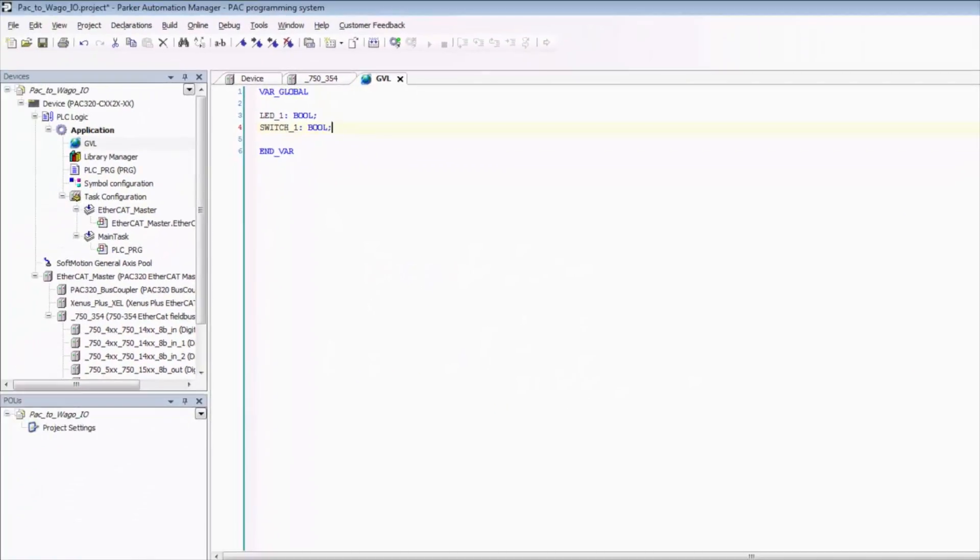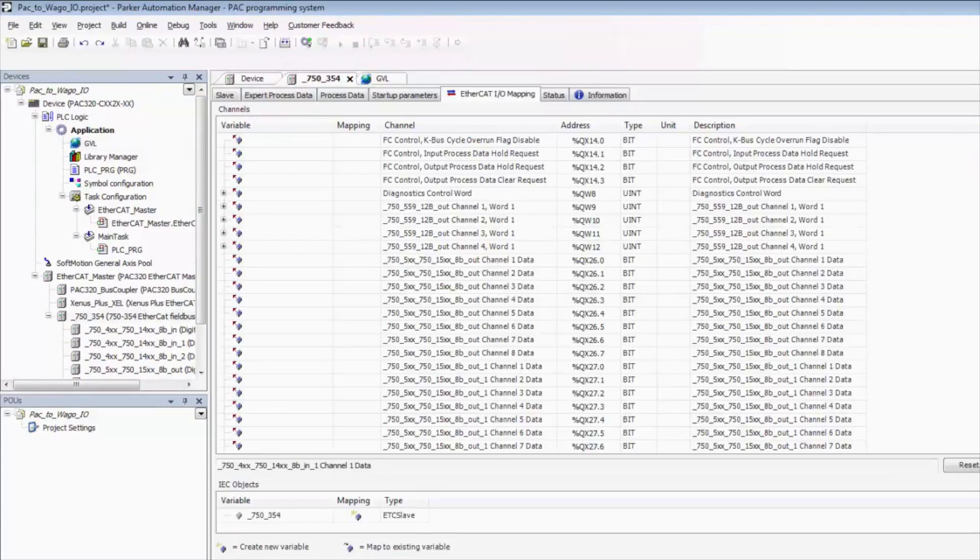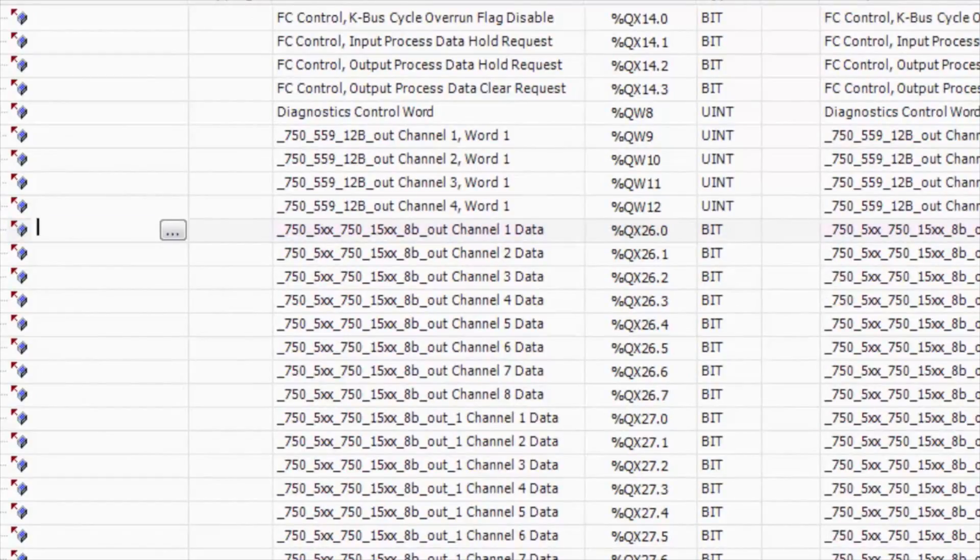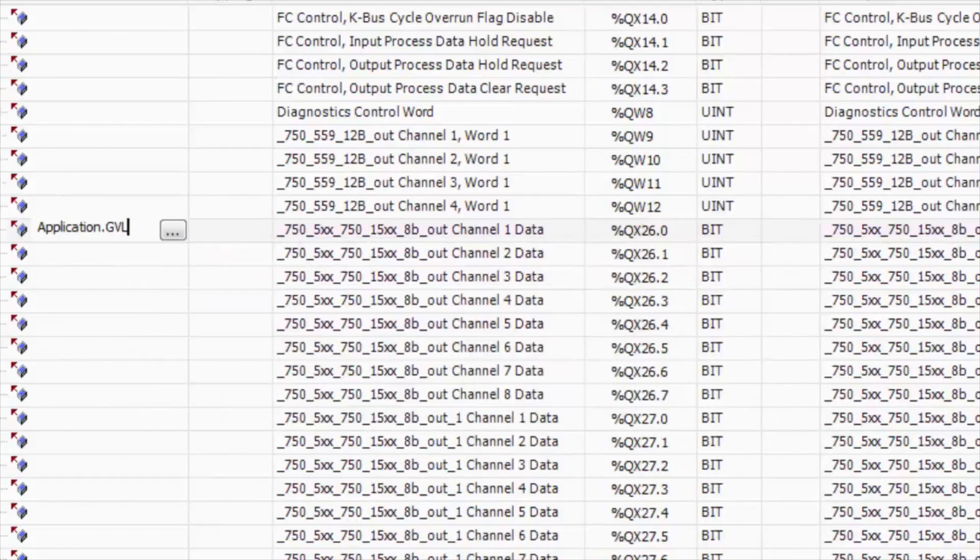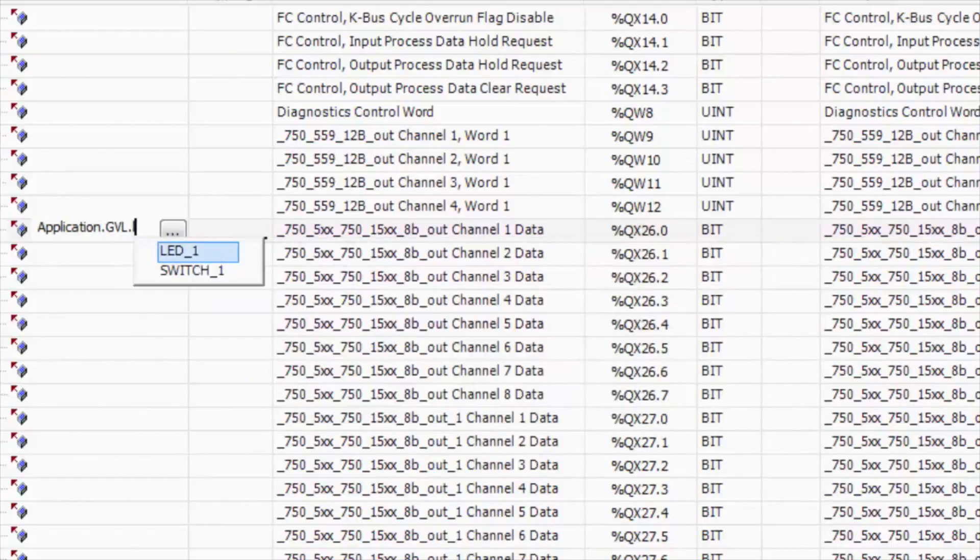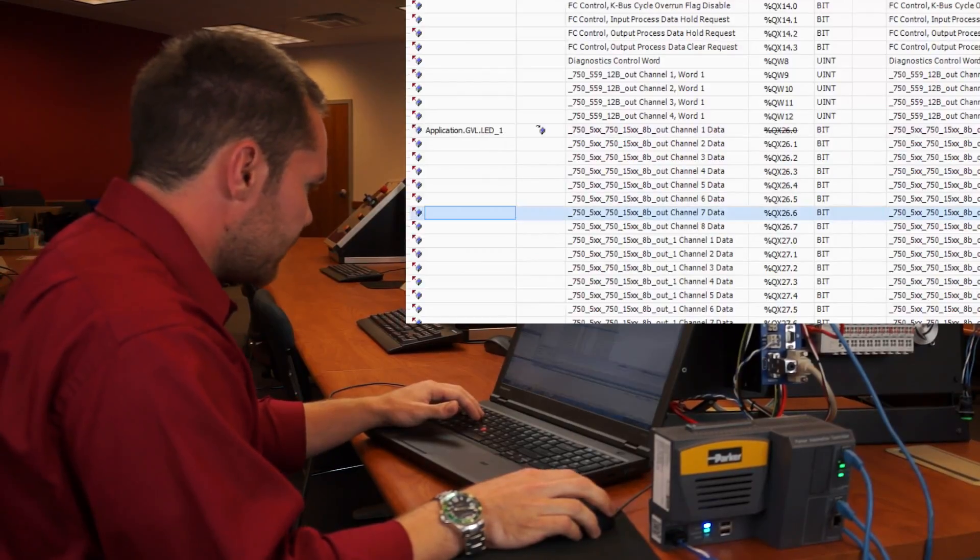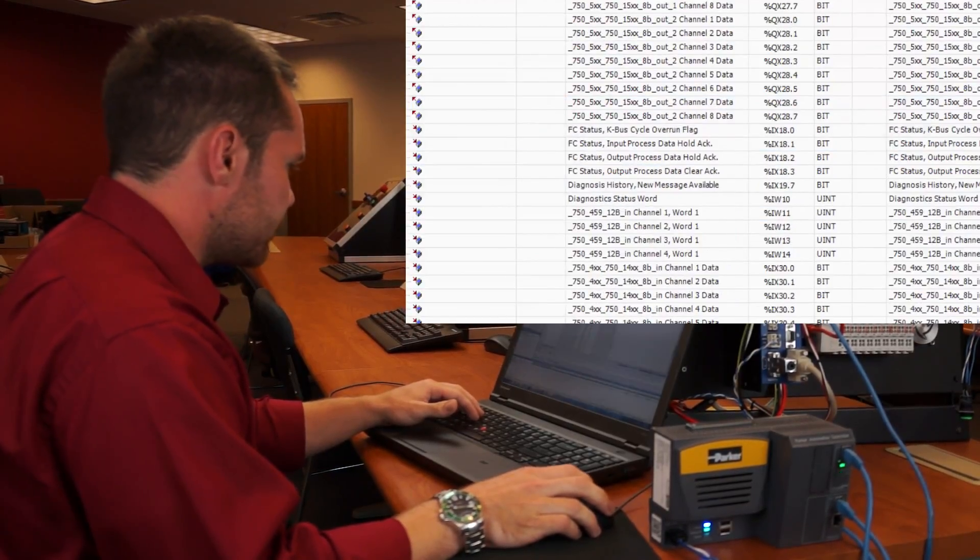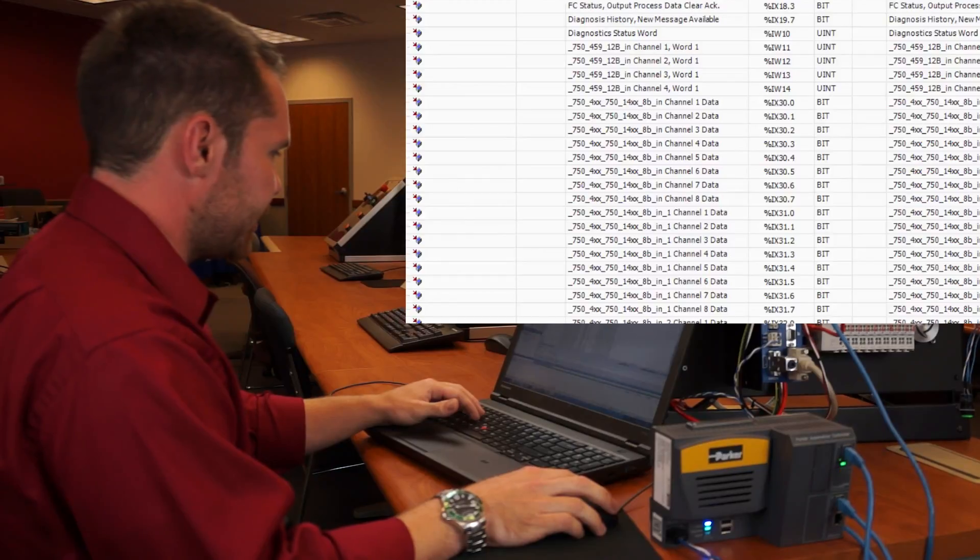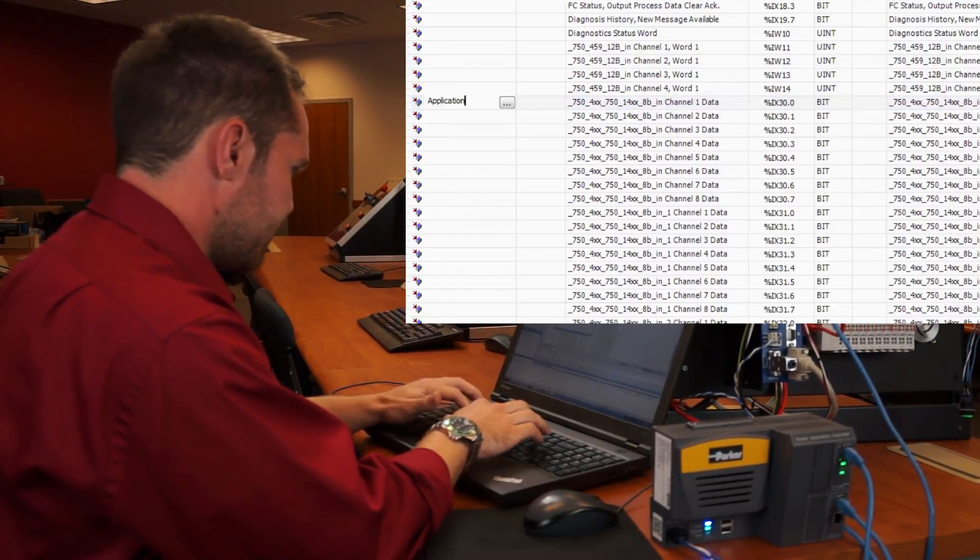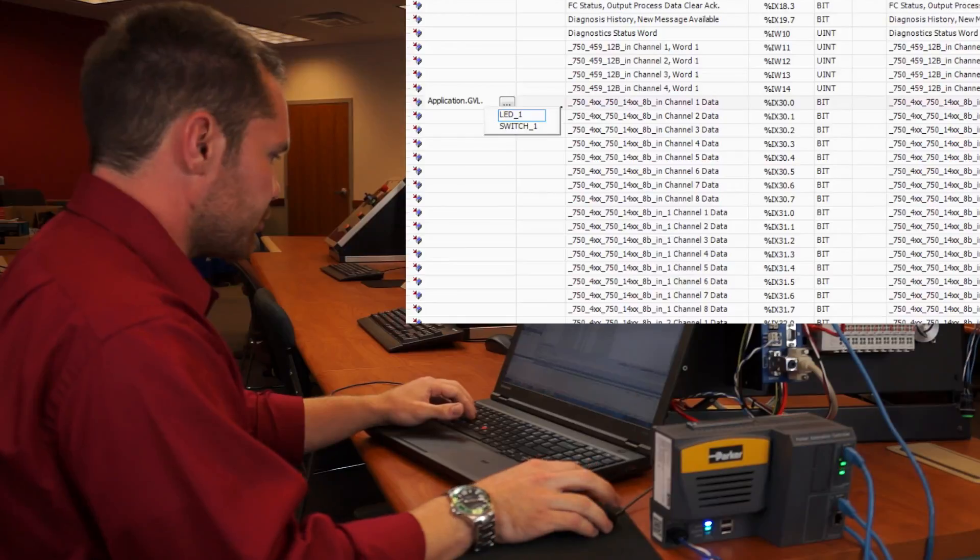Now that we've created our global variables, we can go back to the IO coupler and we can go select our first channel of output, and then we need to select the application, the global variable list, and then we can select our LED output. Double click that and now we can go down to our first input channel here. Double click that, application, GVL, switch1. So now we've assigned our two variables to IO ports there.